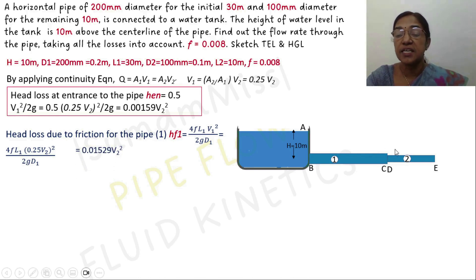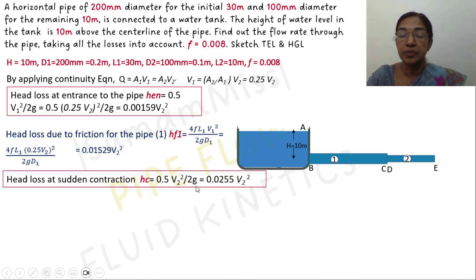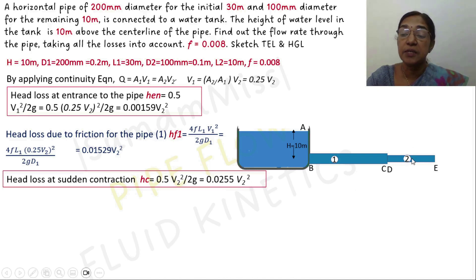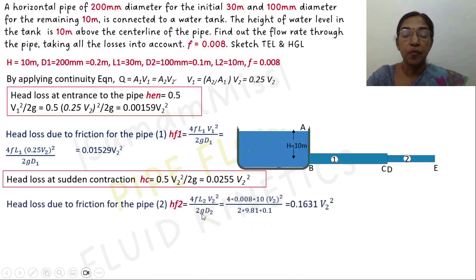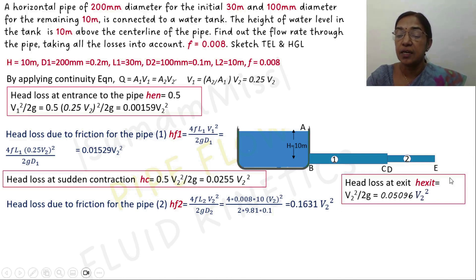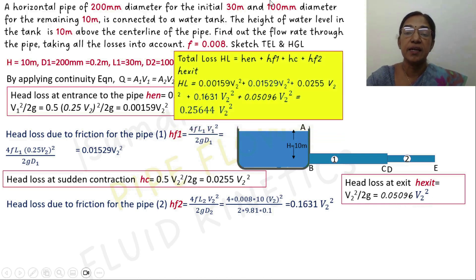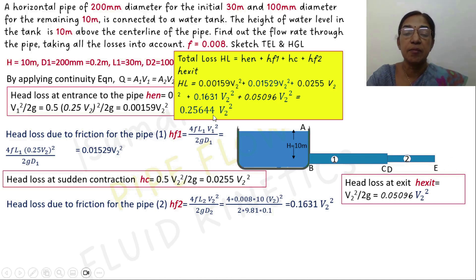The contraction loss at section D is 0.5 V2²/(2g), giving hc = 0.0255 V2². The friction loss for pipe segment 2 is 4fL2V2²/(2g·D2), obtained as 0.1631 V2². The exit loss equals V2²/(2g) = 0.05096 V2². Summing all losses — entrance loss, friction loss in pipe 1, contraction loss, friction loss in pipe 2, and exit loss — gives a total of 0.25644 V2².